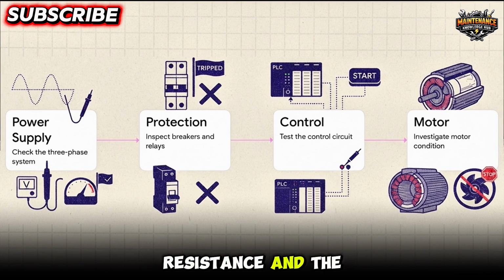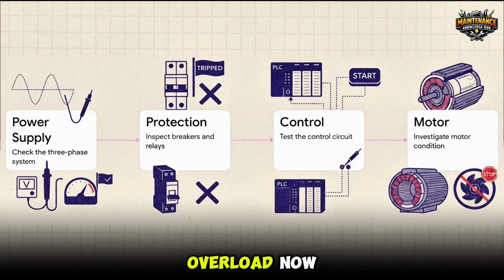Check the winding resistance and the insulation. And hey, don't forget the mechanical side. A seized pump will absolutely cause a perfectly healthy motor to draw massive current and trip the overload.